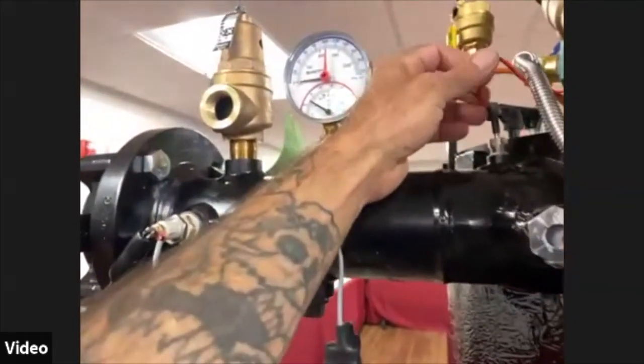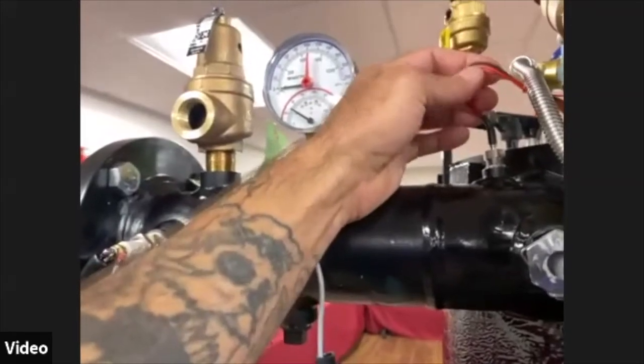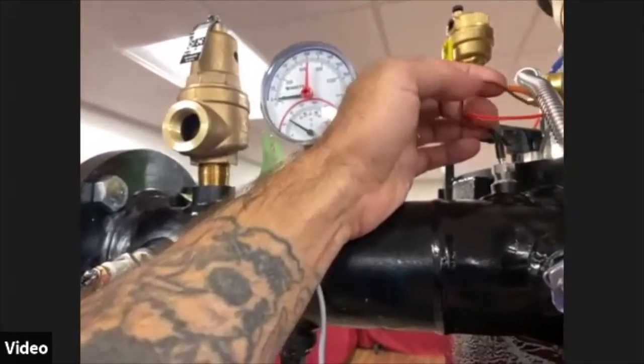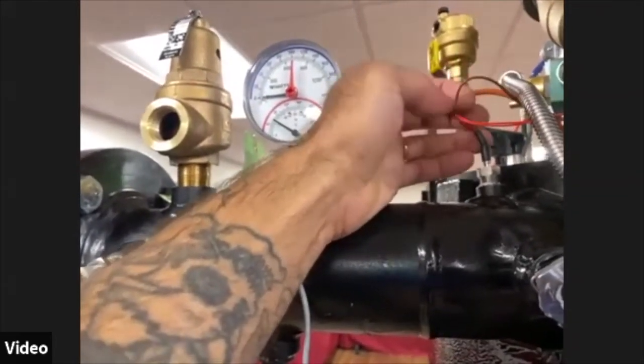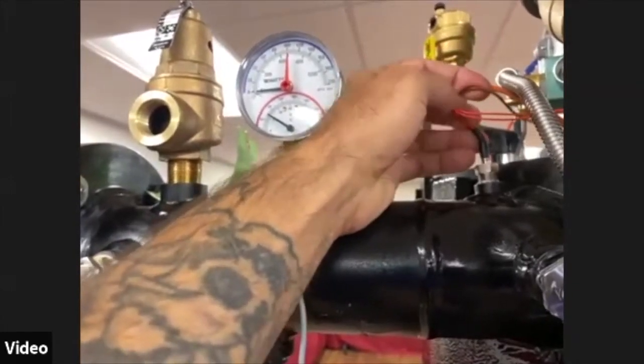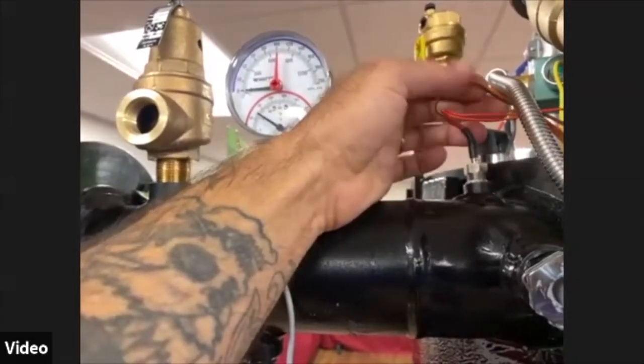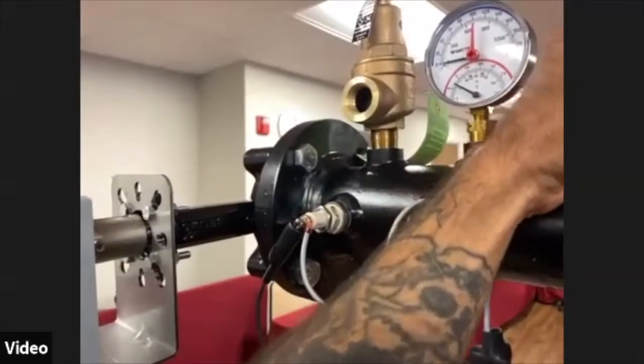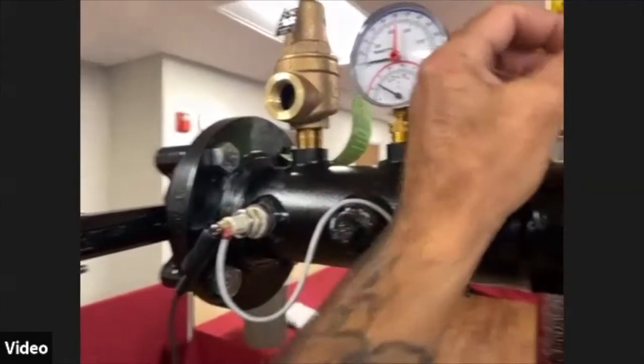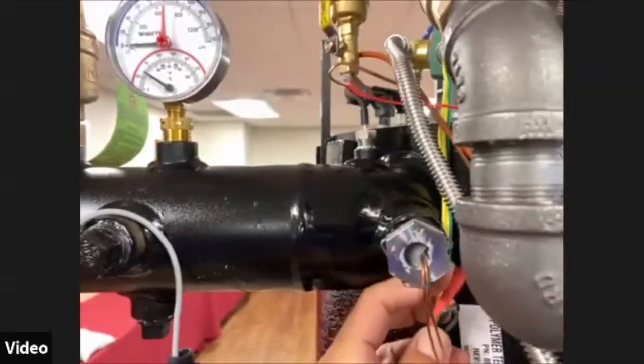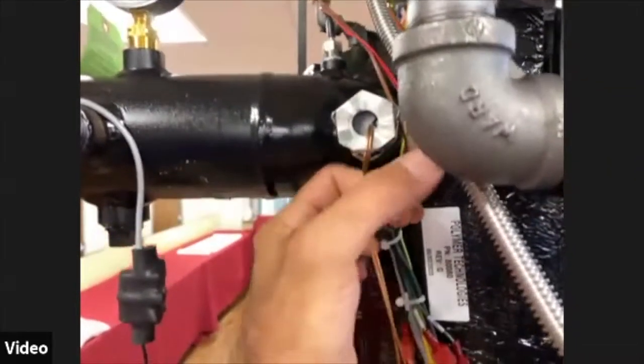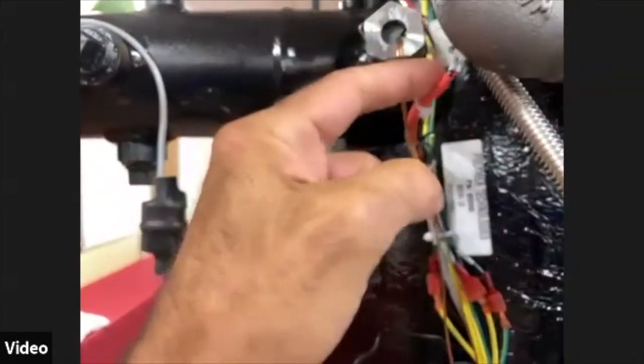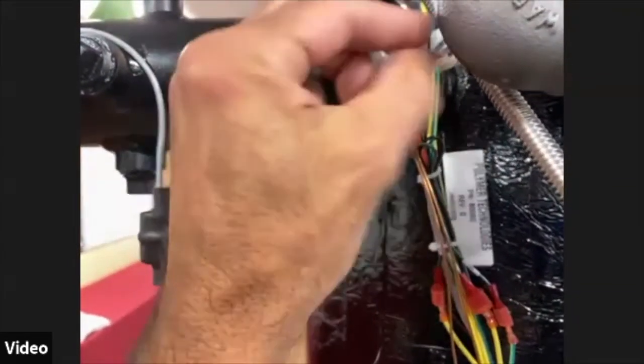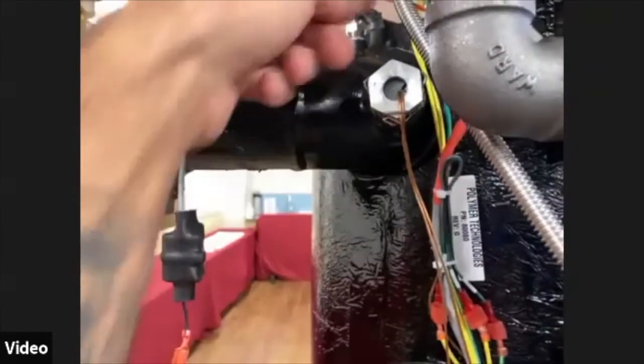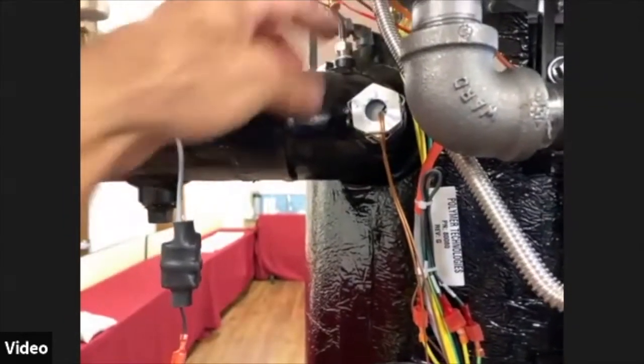This one up here will be our outlet temperature sensor. This is also a dual sensor. So this is outlet, and this is also the low water control, which is on the front. When we come back around, I'll show you where that is too. One of the things I'd like to note in particular is, hopefully you can see this here, there's some red coating on this connector. The red obviously to me would be hot water. That would be your outlet side. That's kind of an indication that it's your outlet.